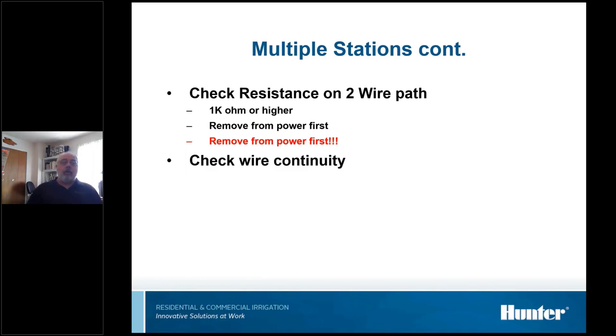Now, checking wire continuity. In other words, if we're down to the point where we think the problem's between two valve boxes, what we're going to do is go to one end of the wire path and twist the two wires together. We're going to literally twist the red and blue wires together. We're going to go back to the other end and check for continuity. When you do that, that reading should be very low. It should be a single digit ohm reading. That tells you the continuity. Or, if your meter's got an audible continuity tone, you can just see if it tones.